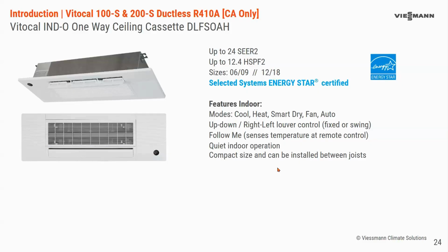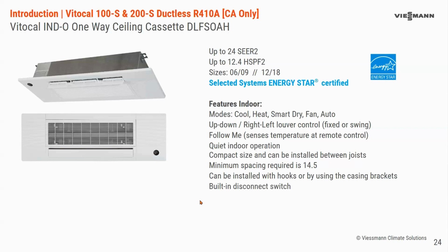Follow Me features, standard quiet indoor operation. The big thing is the size. The form factor can be installed between joists. I have an image of that in the next slide, but current and future joist spaces, this unit can fit in between those. As you see there, the minimum spacing required is 14.5 inches. Installed with hooks or using the casing brackets, has a built-in disconnect switch.